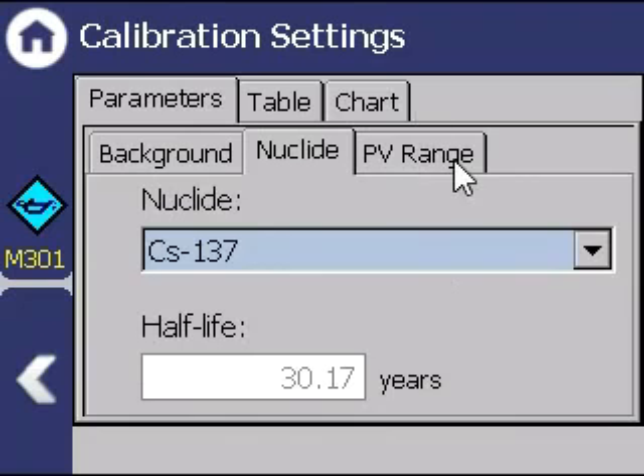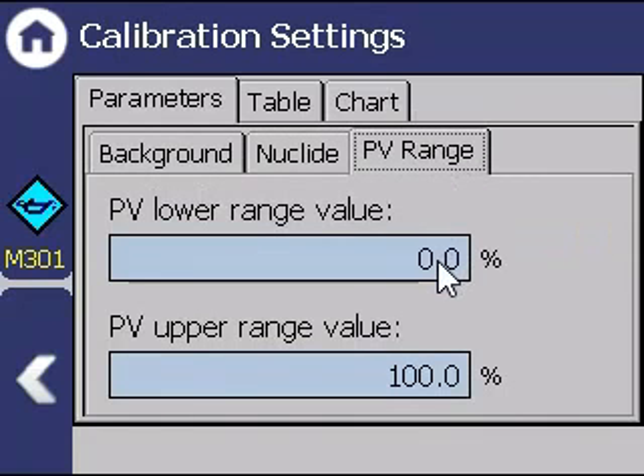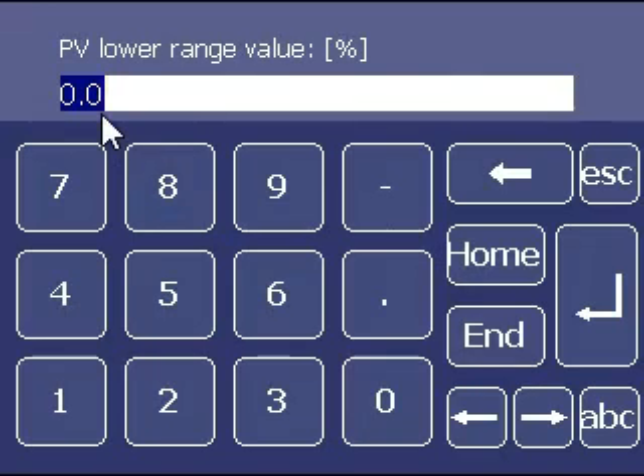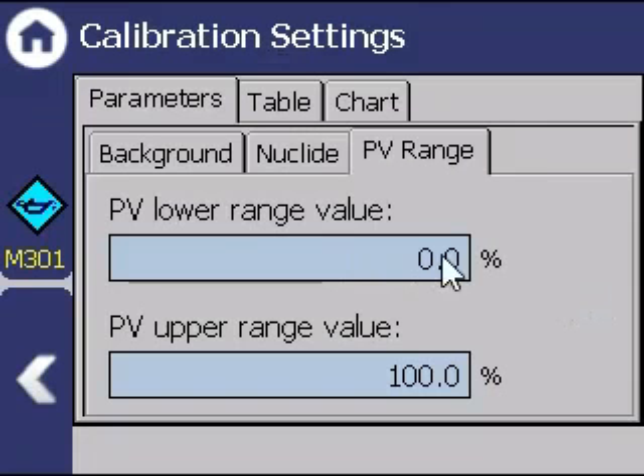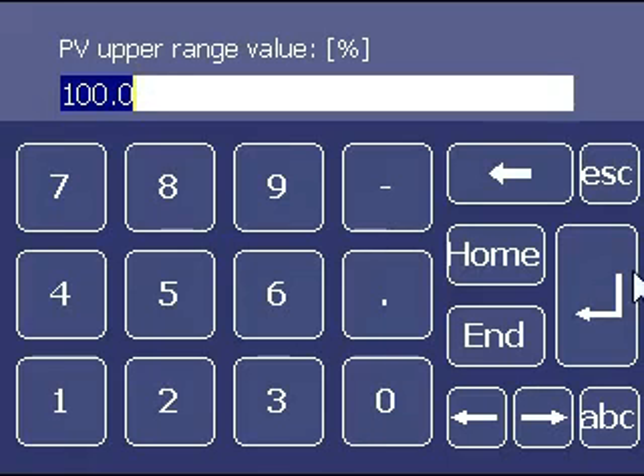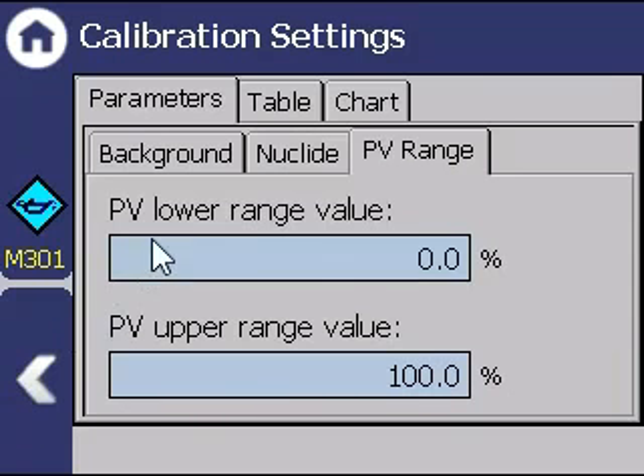Select PV range. This setting will set the scaling for your 4 to 20 milliamp output. Typically, this will be from 0 to 100%. Make sure these settings relate to what the DCS or PLC is expecting on the other end of the output. We will be performing a simple open and closed calibration for this demonstration, which means we have an empty vessel and the shutter is open for our 0 point. Then closing the shutter to simulate a full vessel and read in our 100%.